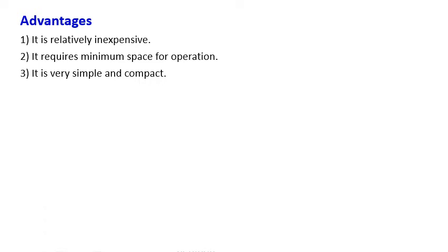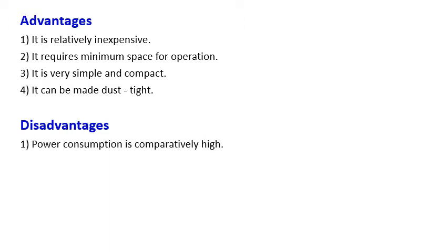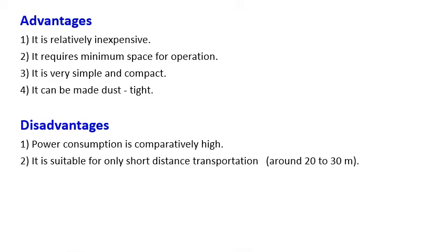Advantages of screw conveyors: relatively inexpensive, requires minimum space for operation, very simple and compact, and made dust-tight so coal powder wastage is avoided. Disadvantages: power consumption is comparatively high, suitable only for short-distance transportation of around 20 to 30 meters — much less than belt conveyors. Wear and tear of parts is more, and jamming may take place, especially when coal has moisture above recommended levels, requiring manual clearing.